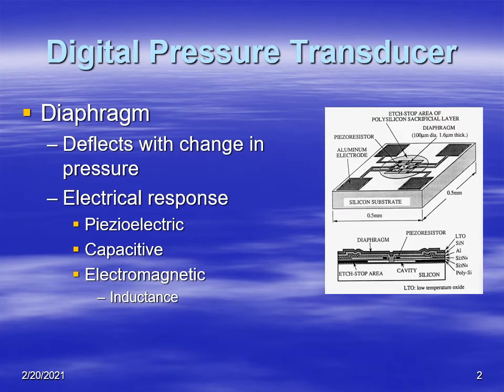A digital pressure transducer makes use of a diaphragm. This is a little flexible piece of material that deflects as pressure changes. As a result, you can get different types of responses depending upon how this instrument is designed. Either you'll get an electrical change that's related to the piezoelectric effect, or there might be a change in capacitance, or maybe even inductance through an electromagnetic type effect.